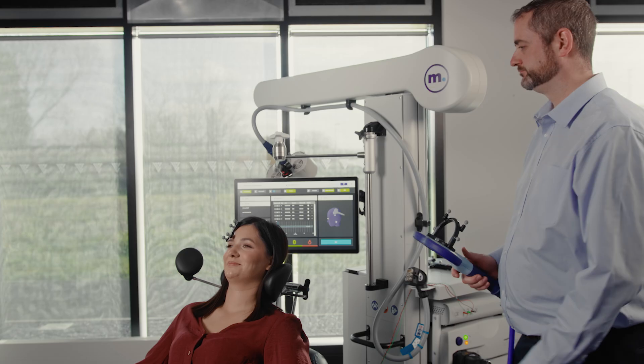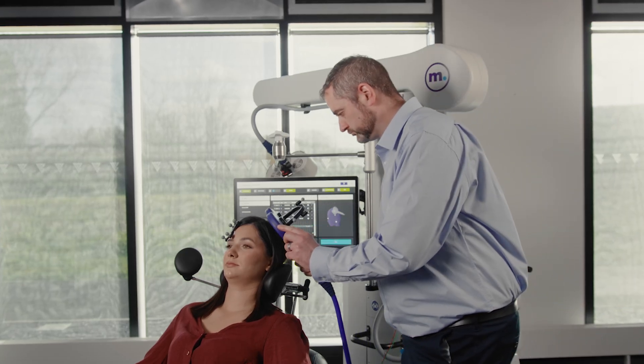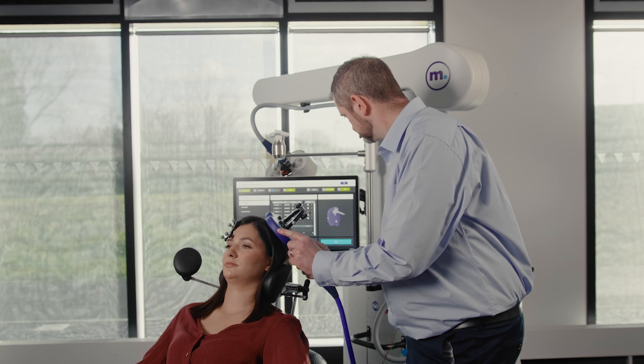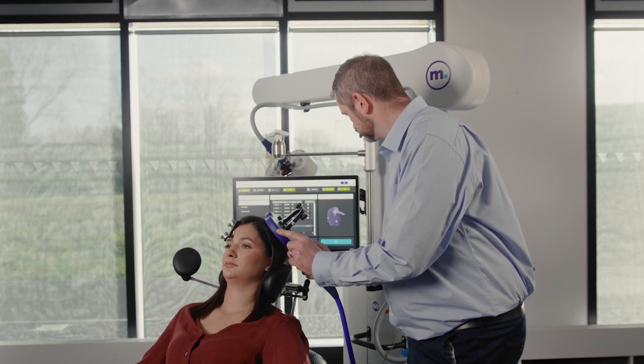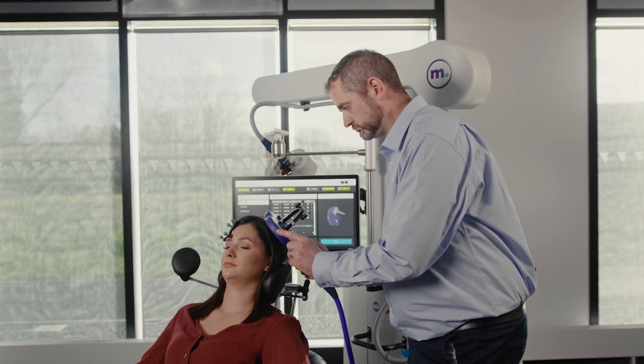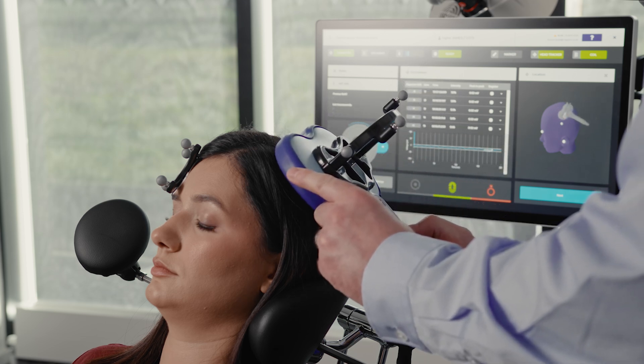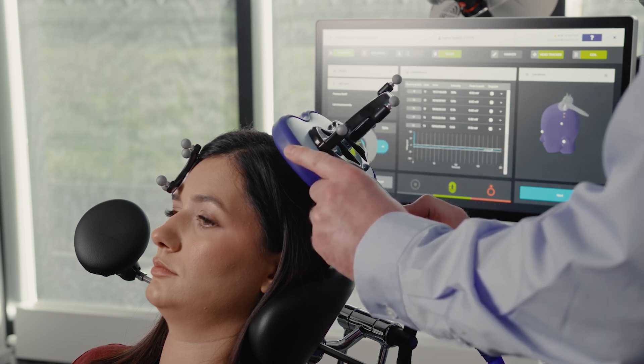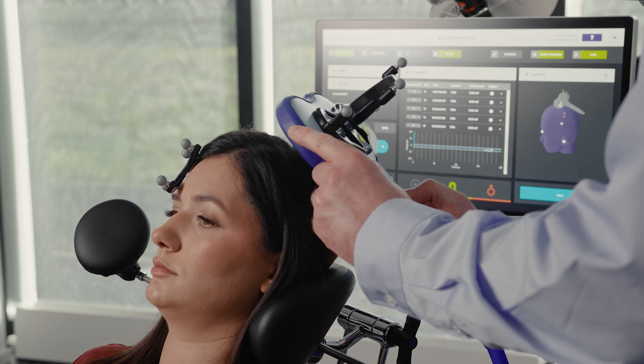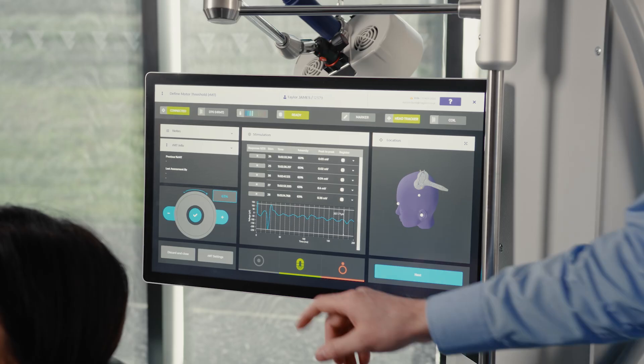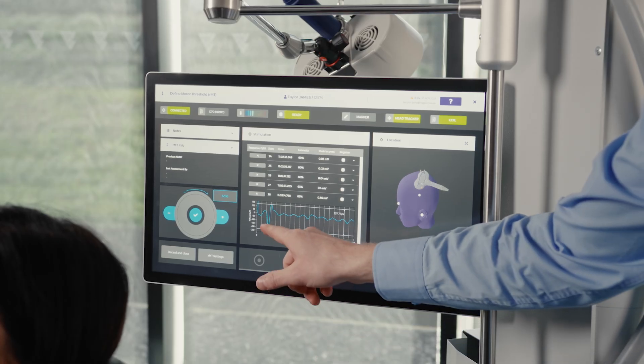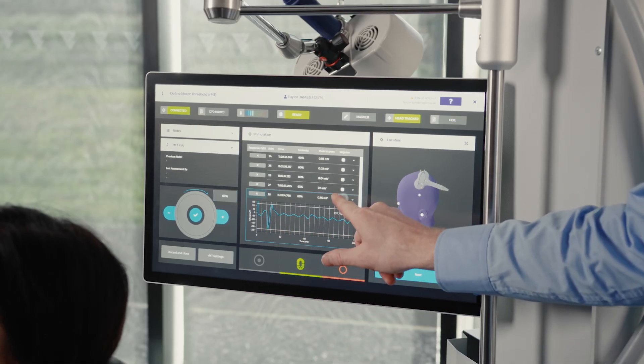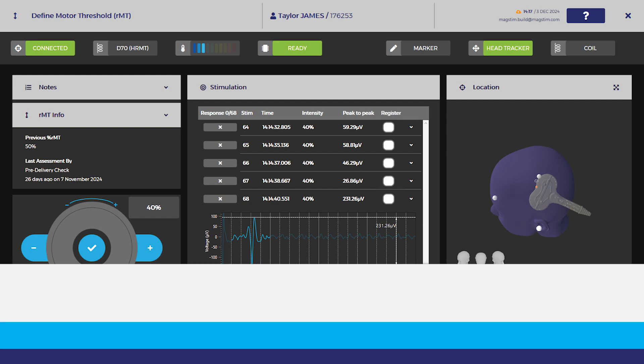Referring to the Horizon UI, move the MT coil so the coil icon is over C3 on the 3D head model. Ensure that the coil is at a 45 degree angle to the midline and tangential to the curvature of the head. Press both multifunction buttons on the MT coil to deliver a pulse. When delivering pulses, watch the stimulation panel on the Horizon UI, observing for a clean EMG response. A clean response should have an amplitude greater than 50 microvolts.